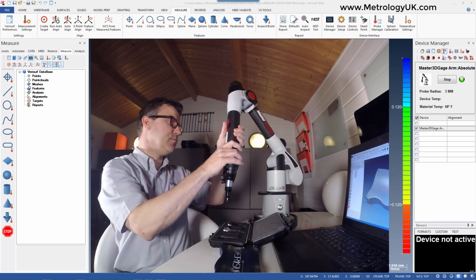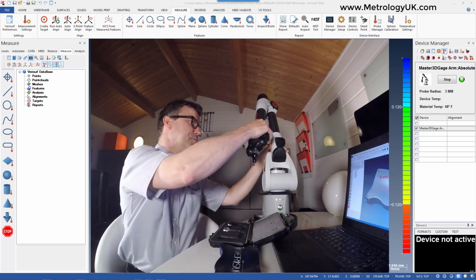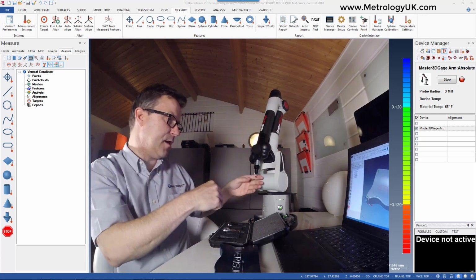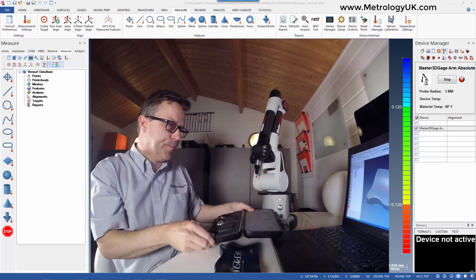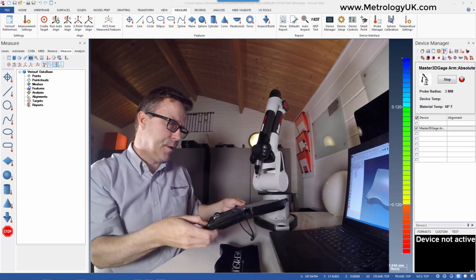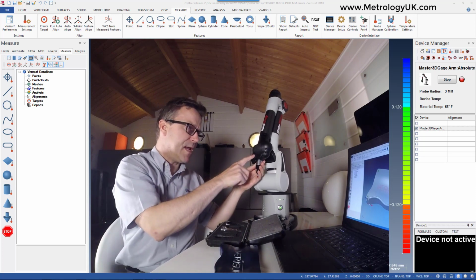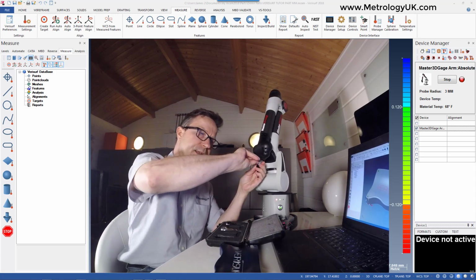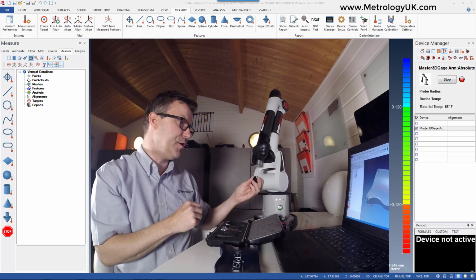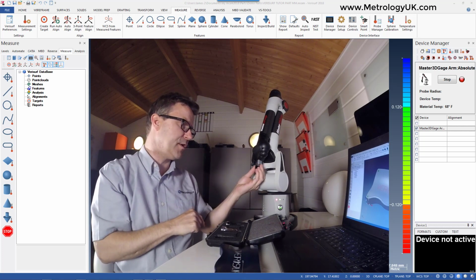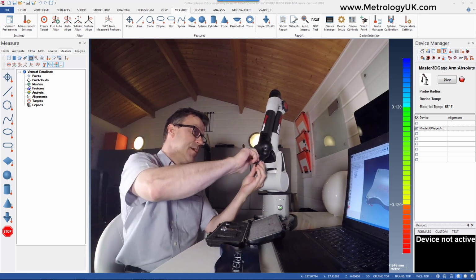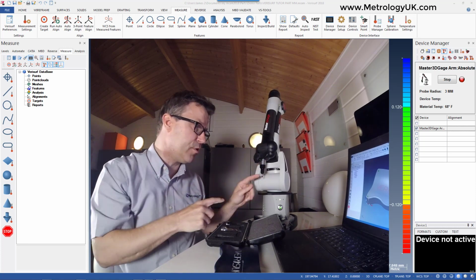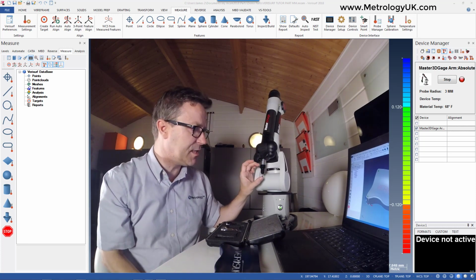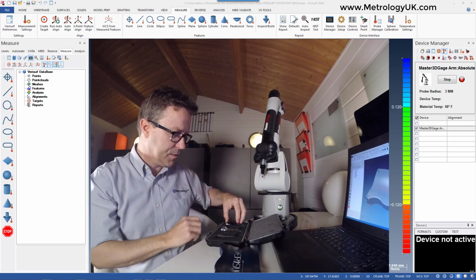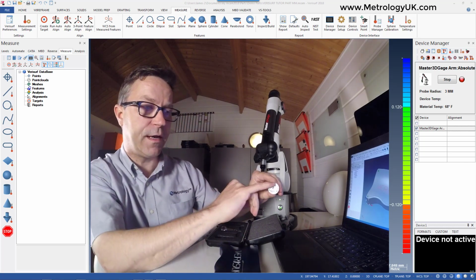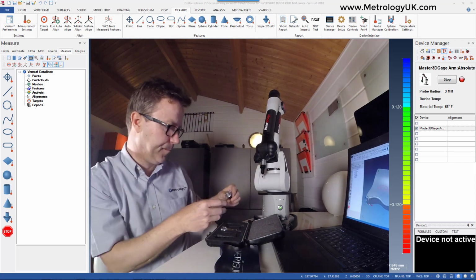The system itself comes with 3 different probe types, a 6mm, a 3mm and a reference probe, like so. It has a quick release mechanism which allows you to quickly release the probe and return it or change the probe to a different type very easily. The information regarding the probe and the calibration is kept within the chipset of the actual probe itself. As you can see, it has a hot connection right here.